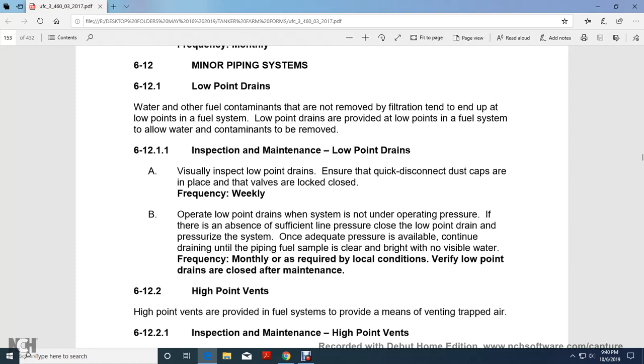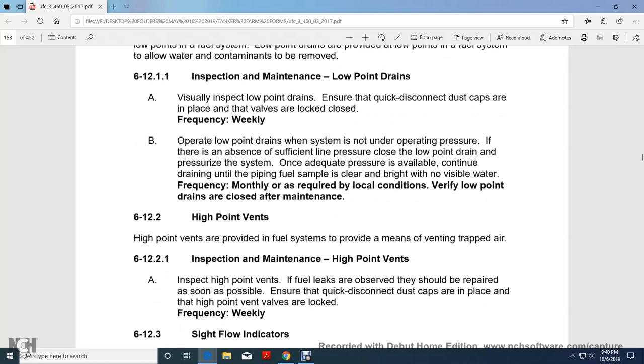In a pressurized system, when adequate pressure is available, continue the drain until the piping fuel sample is clear and bright with no visible water. Frequency: monthly or as required by local conditions. Verify low point drains are closed after maintenance.